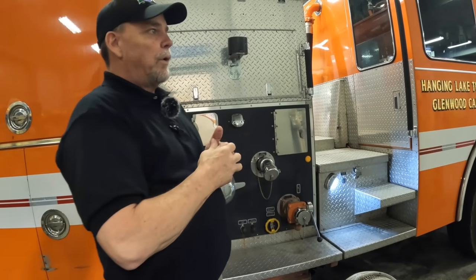Yeah. We have four fans per each bore. So the four fans, all four together running at high speed, will pull a million CFM. Wow. And we can push air plus also supply air. So depending on where the fire is in the bore, we can clear the smoke for the firefighters. Wow, okay. And for people being able to escape. So if you like, we can go upstairs. I can show you the control room. Yeah, let's do that. Absolutely.